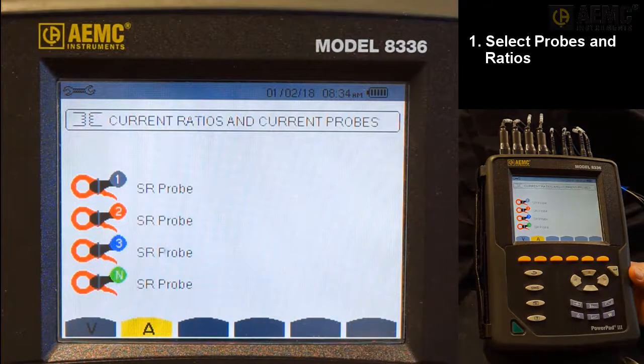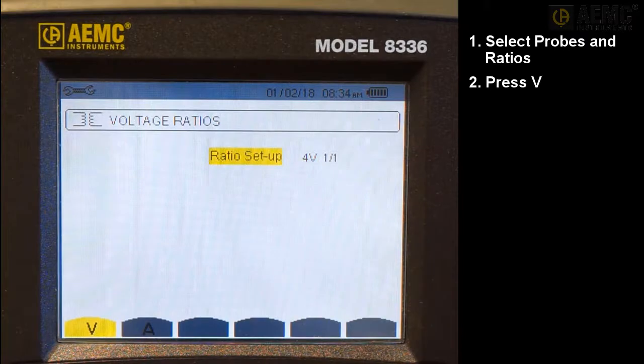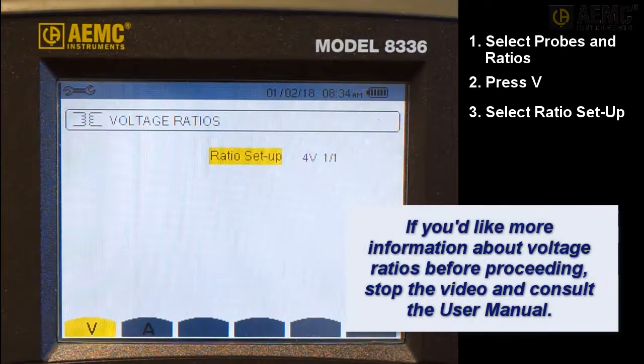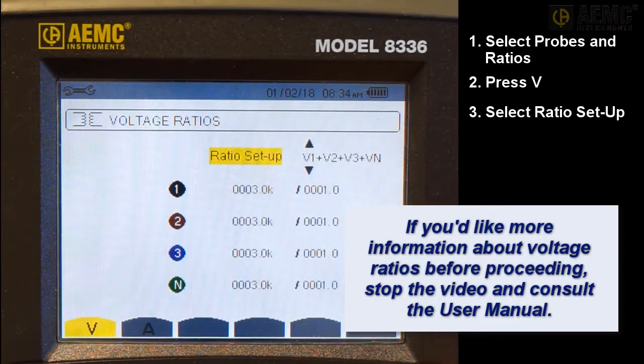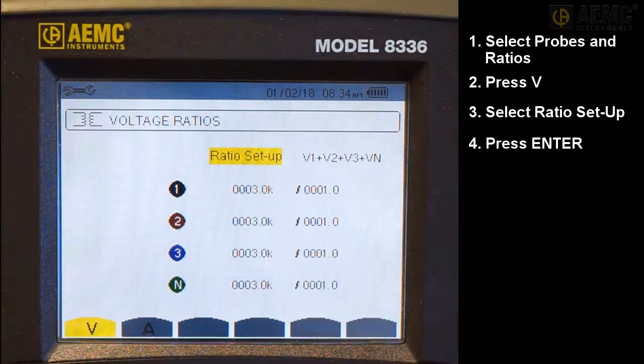This screen lists all connected sensors, which are automatically detected and identified by the instrument. Press the first yellow button on the left, under the V icon, to display the voltage ratios screen. This lets you select the primary to secondary ratio for voltage channels. You can also choose whether to use the same ratio for every line or assign a unique ratio for each. By default, the ratio setup field is highlighted. Press Enter to select this setting and use the arrow buttons to change it. In our demonstration, we will choose to have different ratios for every line. Press Enter to save the selection.